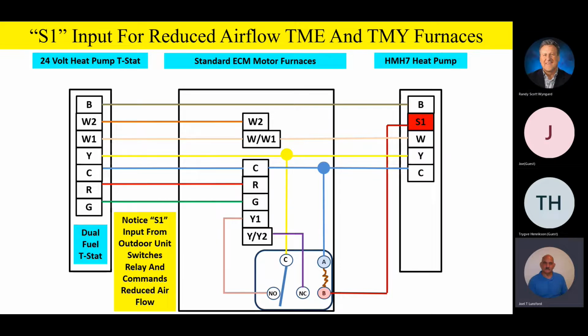But just like we had before, let's say we're in the cooling mode of operation. So in the summertime, a mild day, we get an S1 output from the outdoor unit. It switches that relay. We reduce that airflow inside to more perfectly match the airflow requirement with the reduced capacity outside. So that's where the real comfort comes in.